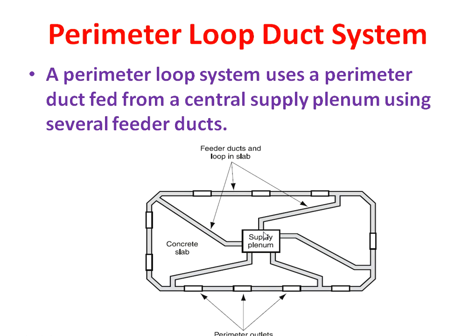This is the image of a perimeter loop duct system. There is one central supply plenum. The function of the supply plenum is to receive heated or cooled air from the AHU and supply it to the perimeter outlets. The air is supplied from the supply plenum to the perimeter ducts through feeder ducts — there are four perimeter feeder ducts.